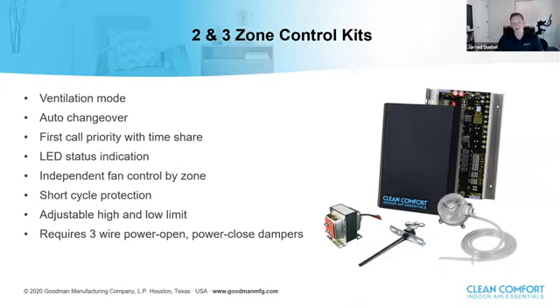We have short cycle protection. Just like most thermostats, the last thing we want to do is run into a situation where we're short cycling our equipment, because that can cause a lot of wear and tear. So we have a 3-minute short cycle protection built into our zone panels. It's not going to allow the zone control system to just keep calling back and forth and kicking on the equipment.